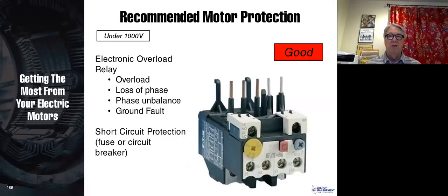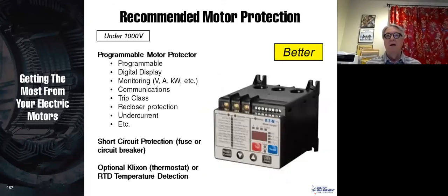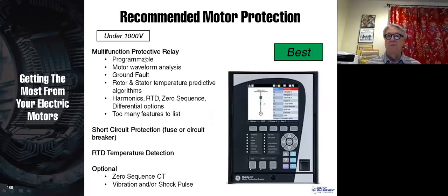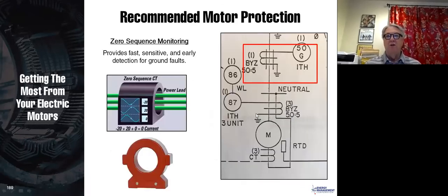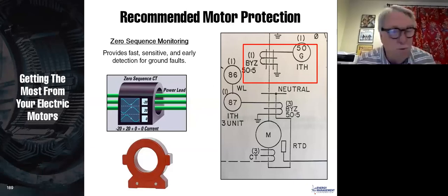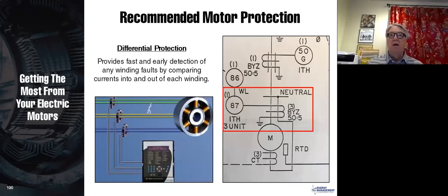Recommended motor protection for under 1,000 volts. This is typical, you get solid state relays. If you want something more sophisticated, then that's your better. And if you want to get very sophisticated, then there's your best. This is also zero sequence monitoring, which is recommended for all medium voltage motors, and a very great way to detect motor insulation failure early, while the cost to rewind it is cheap because you haven't done a lot of damage.